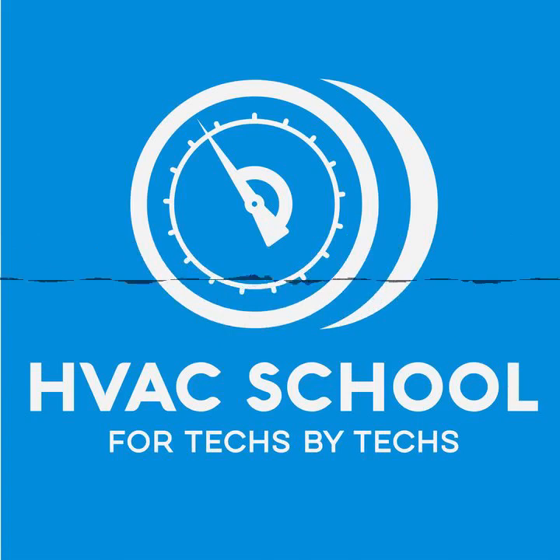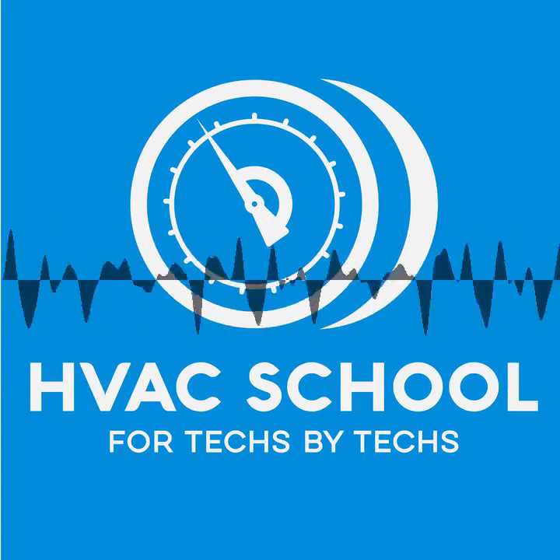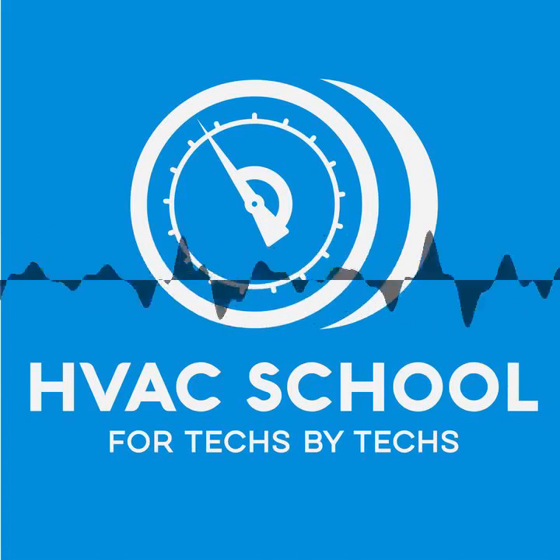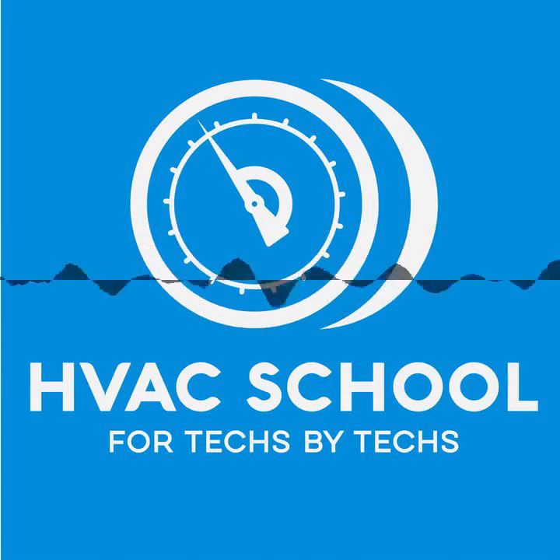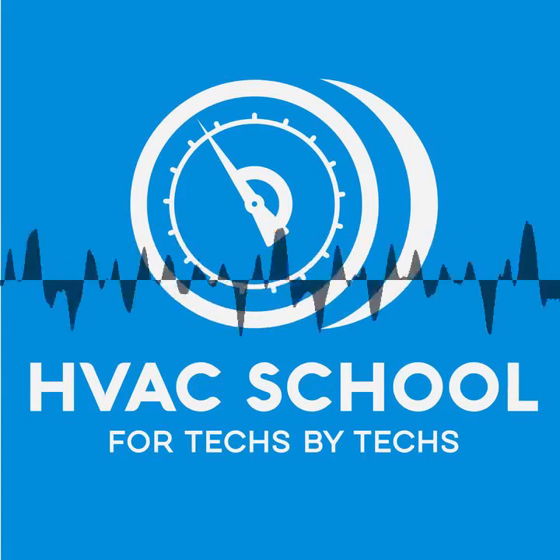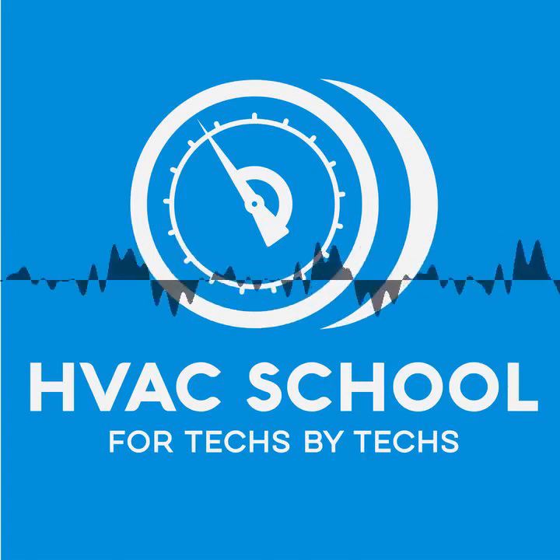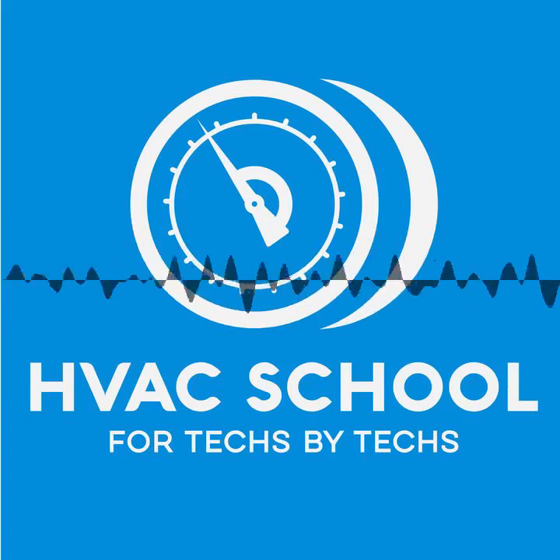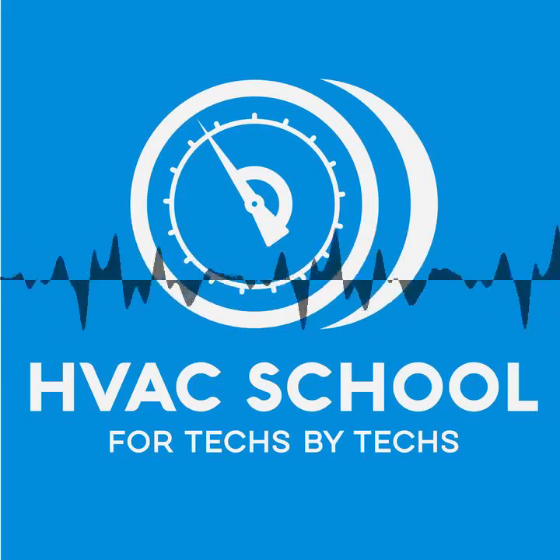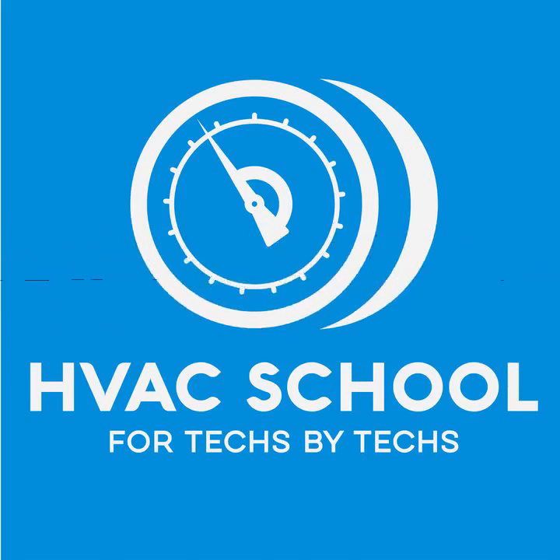And what are the most common failures that you see? Most of it's electronics because we have bad power here. Inverter power boards can go, or a wire can burn out and short something. Compressors, very, very rare. I haven't seen one yet, but I've heard of places that had compressor problems, which is mostly the inverter power module. Yeah, I haven't seen very many compressor problems. If you have bad power from the grid, it nuisance trips the units sometimes, the power modules. But nothing big that I've ever seen, like a burnout or something like that.